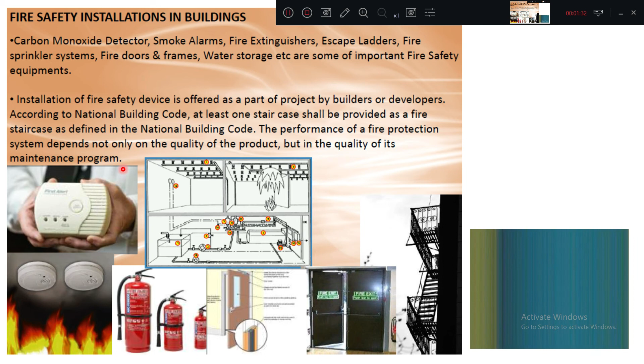The performance of the fire protection system depends not only on the quality of the product but on the quality of its maintenance program. So if the product is good but maintenance is not done correctly, the total system will get collapsed. So both quality of product and quality of the maintenance program should be good - then only it will function properly.